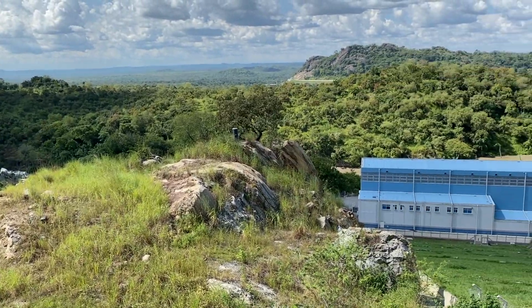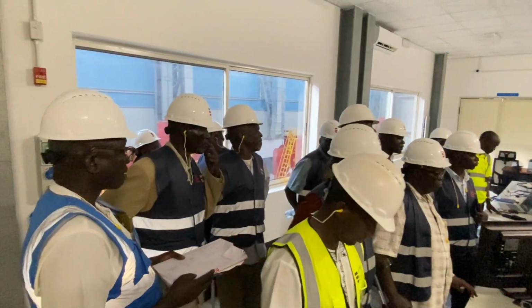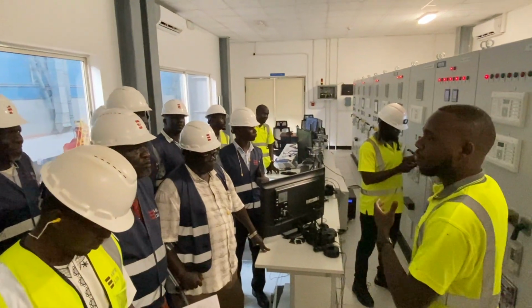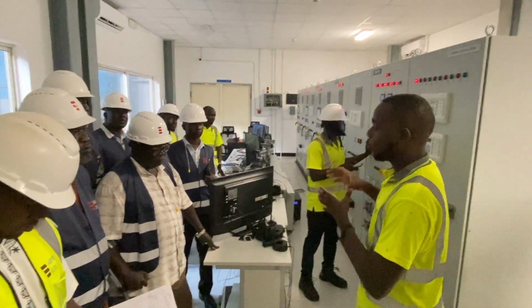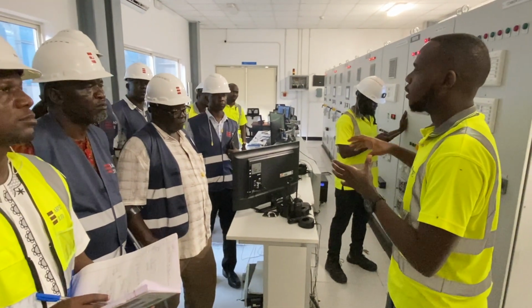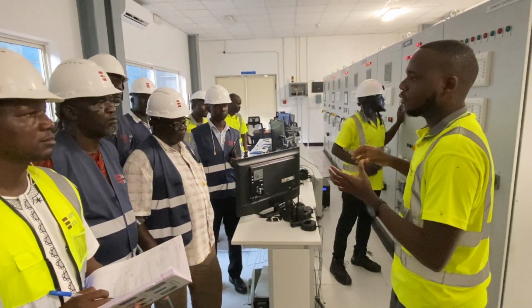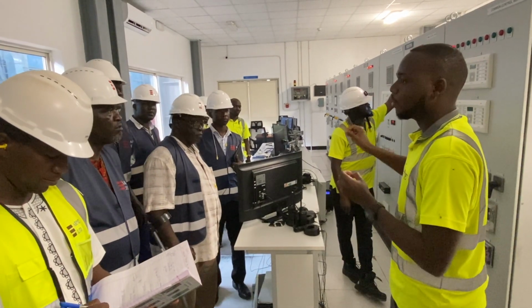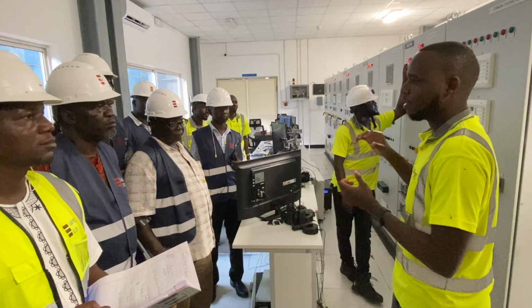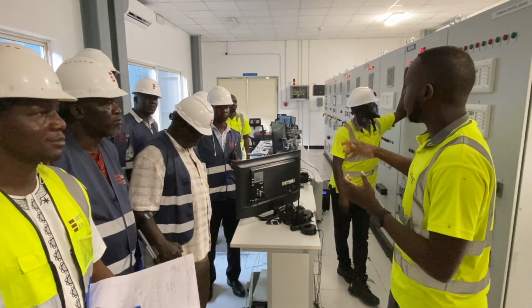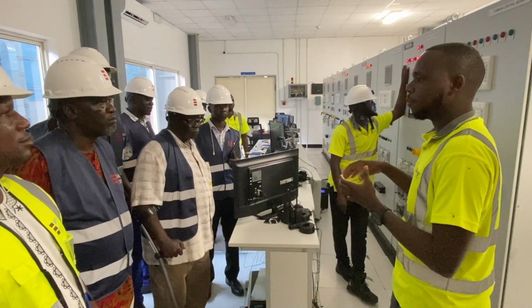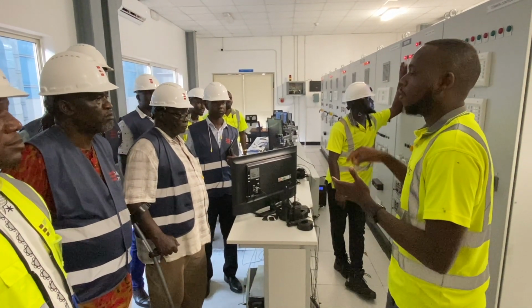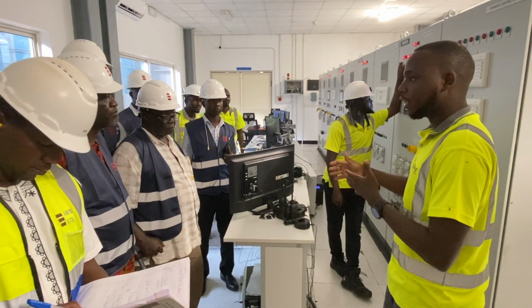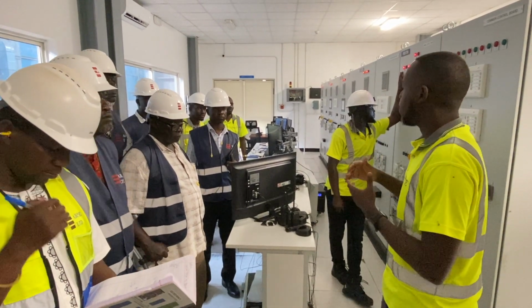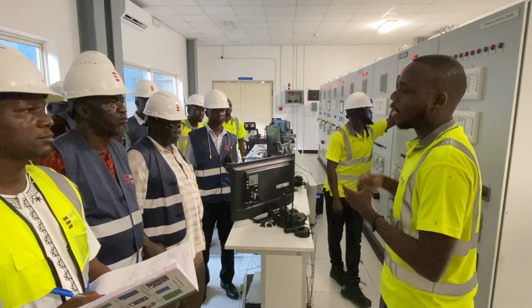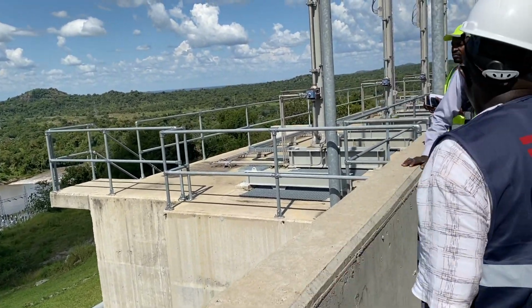At the moment, we are generating 39.4 megawatts, so we divert only the water needed to generate that, approximately 97 to 100 cubic meters per second. Currently, because we have high inflows, our net head is a bit low. Normally at HPP2 we're supposed to generate 41 megawatts with 100 cubic meters per second of water, but because our net head is a bit low, with that same flow we can only generate 39.